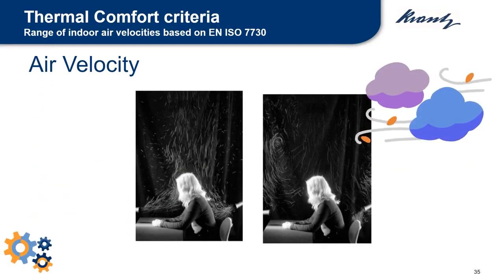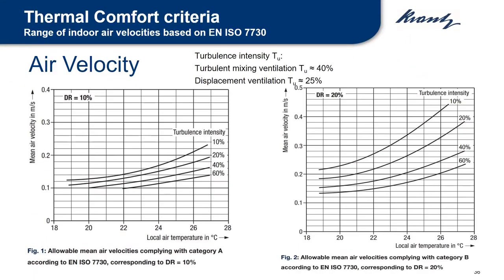Air velocity. Air velocity is another aspect which makes a big impact on a person's comfort levels. The faster the air moves, the greater the heat exchange will be. The fluctuations of airspeed, which are characterized by turbulence intensity, increase the sensation of draught and thus affect the thermal comfort. The graphics beside show us the maximum allowable indoor air velocities to meet the corresponding category A or B. Category A corresponds to DR, draught rating, equal to 10%, category B to 20%. For example, to achieve category B at a temperature of 22 degrees Celsius and an air velocity of 0.2, we will have a turbulence intensity between 20% and 40%.